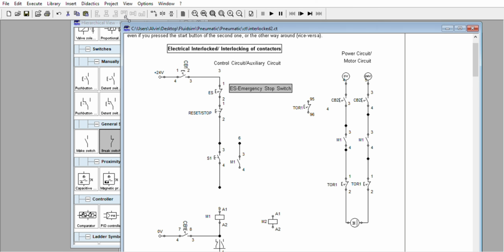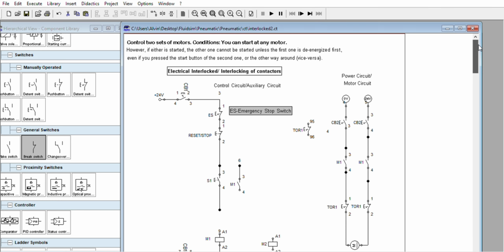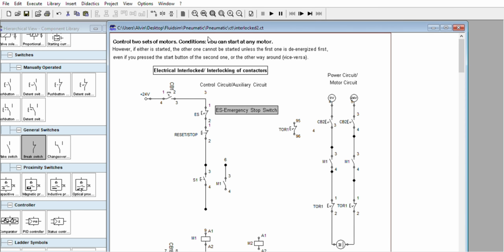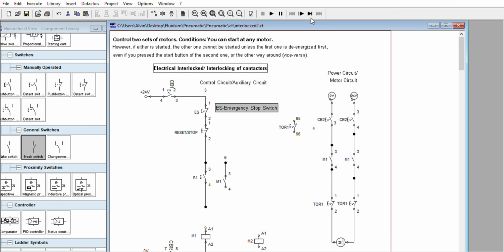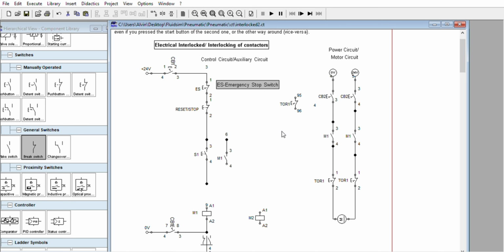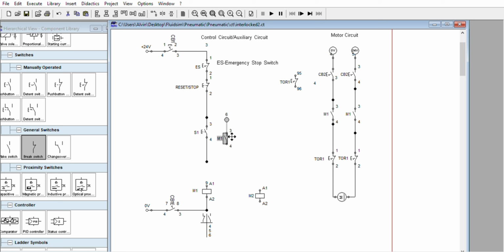Let's say for example this is the condition: control 2 sets of motors. You can start at any motor, however if either is started, the other cannot be started unless it is de-energized first. You will make the standard start-stop control for motor number 1 and copy that for motor number 2, also the power circuit. You will supply thermal overloads later, 2 thermal overloads or 1 overload relay. Standard start-stop, let's say that is the condition only.